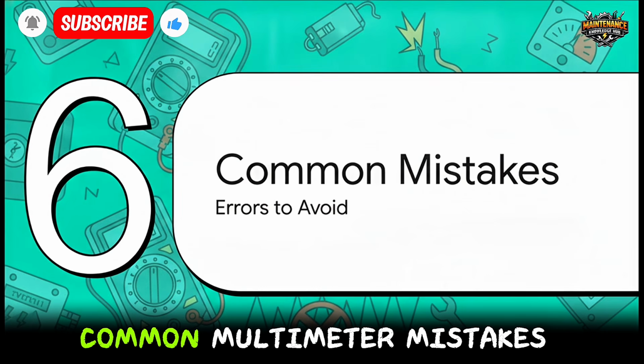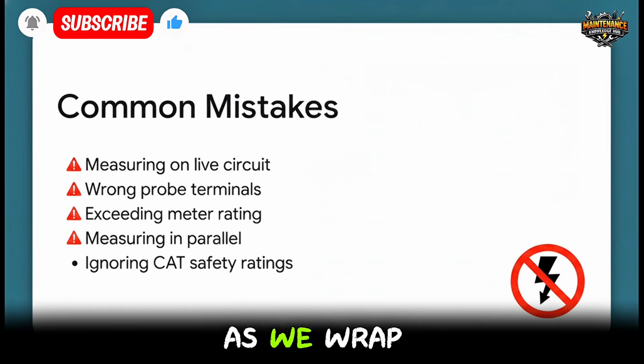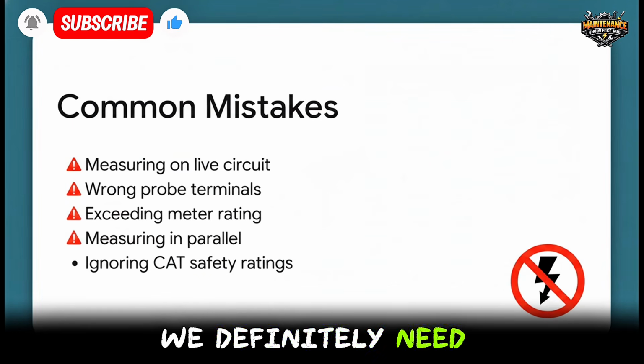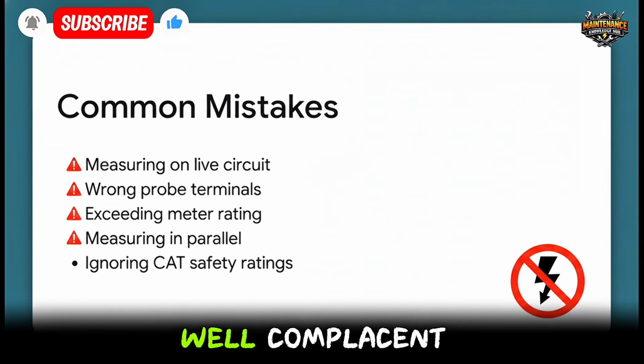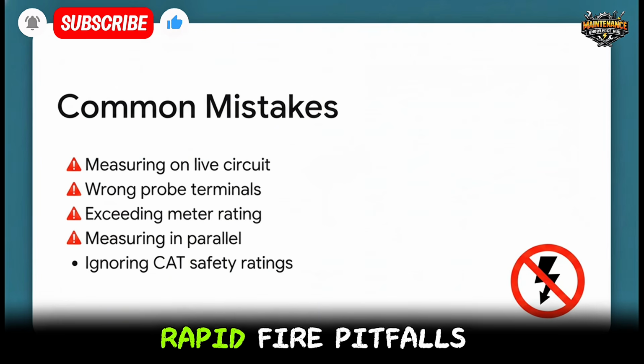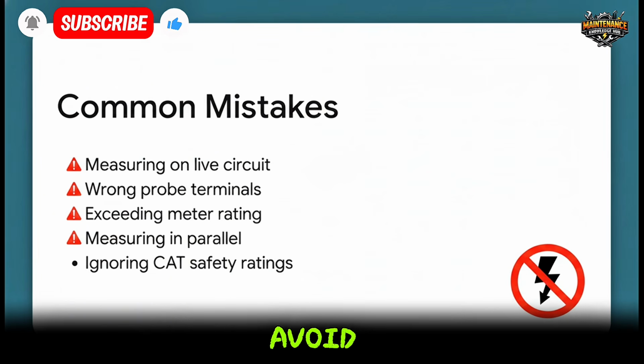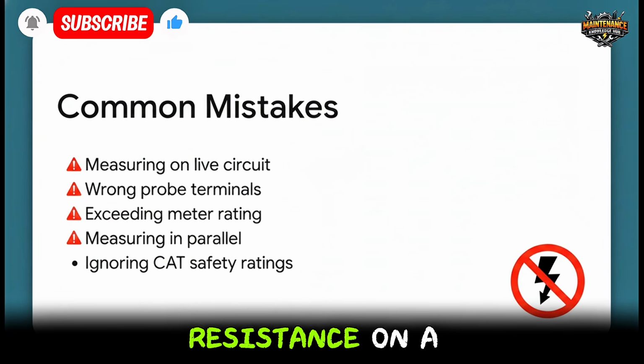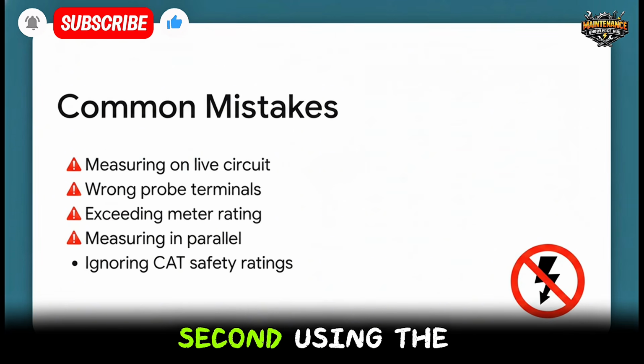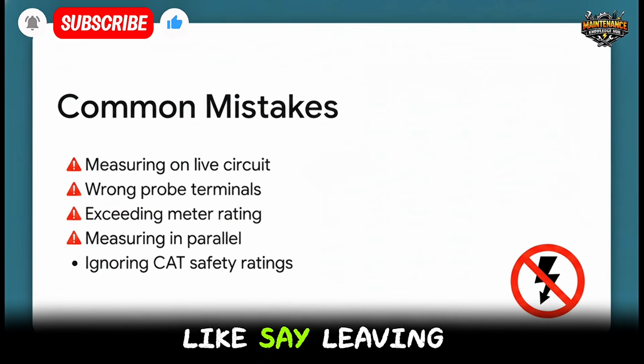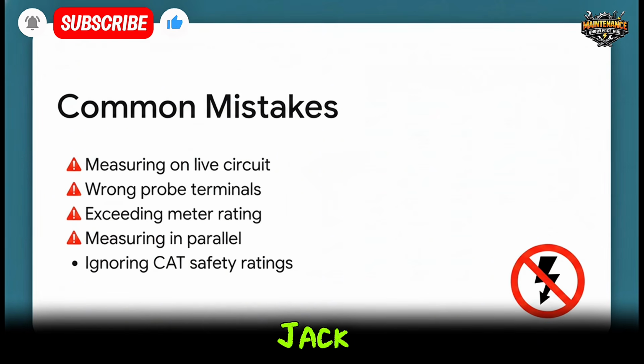Section 6, common multimeter mistakes. As we wrap up this explainer, we definitely need to talk about what goes wrong when we get, well, complacent. These are the rapid-fire pitfalls you absolutely must avoid. First up, measuring resistance on a live circuit. We already covered why that's a disaster. Second, using the wrong probe terminals, like, say, leaving the red probe in the amps jack while you're trying to check voltage. Don't do it.